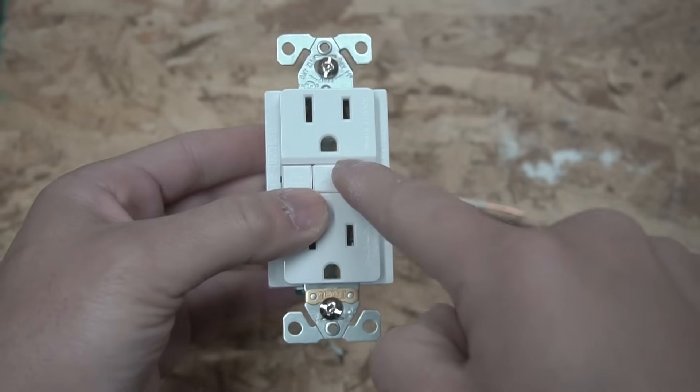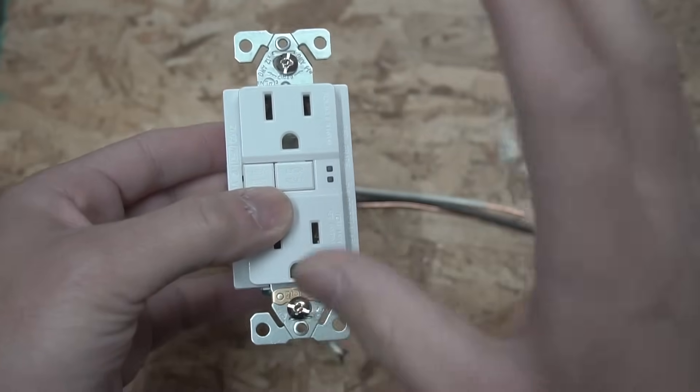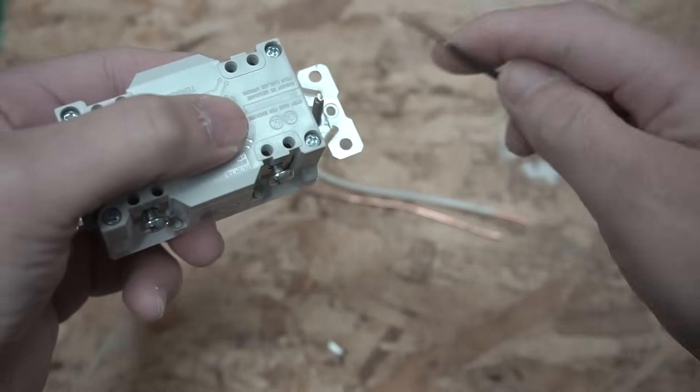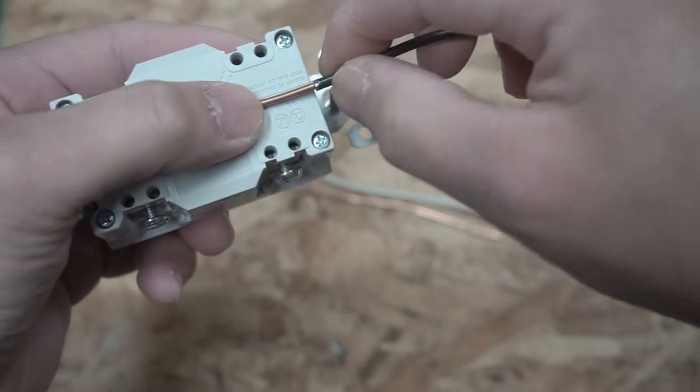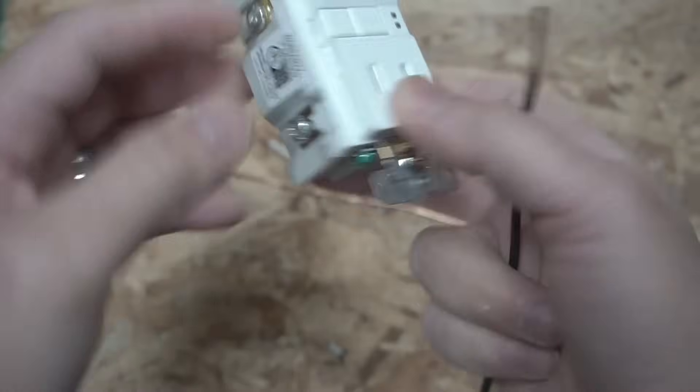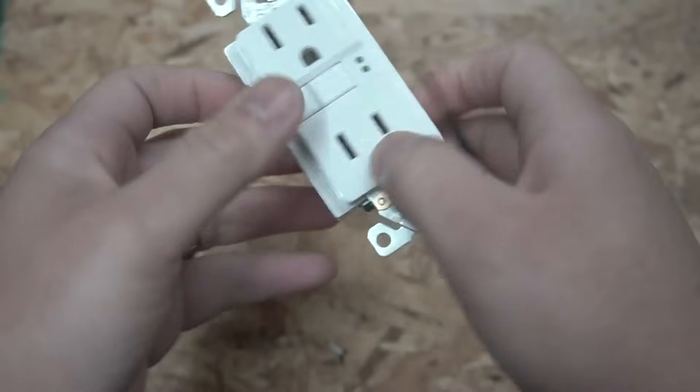We're going to install pigtails onto this GFCI before we install it into our electrical or J-box. And you can tell that there is a strip gauge right here for the back wire. So if we take our hot wire and you strip it, make sure that it's on that length. We're going to be installing the hot on the brass and the neutral white onto the silver.